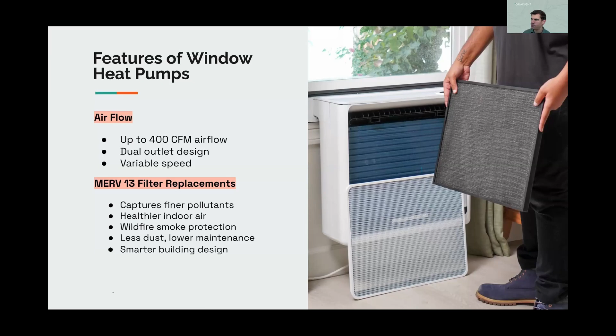There's a major focus in these designs on minimizing air leakage and heat conduction through the window. I talked before about PTACs, which have a large opening, a couple feet wide and tall, to fit a package terminal AC or heat pump through, and that's very leaky. Here, we're looking at just 2 inches or so high across the width of the window, and a lot of design work has gone into making sure the air and temperature leakage through that pass-through is minimal. It's much lower than a PTAC. We estimate it contributes about a 2 to 3% loss in worst case system efficiency, so really a minor change.